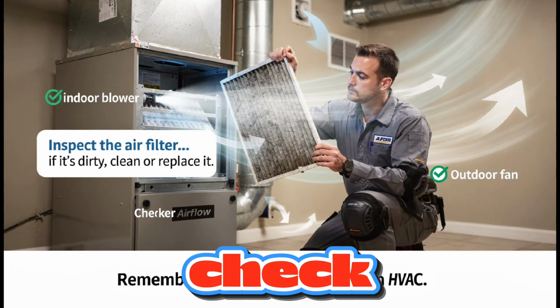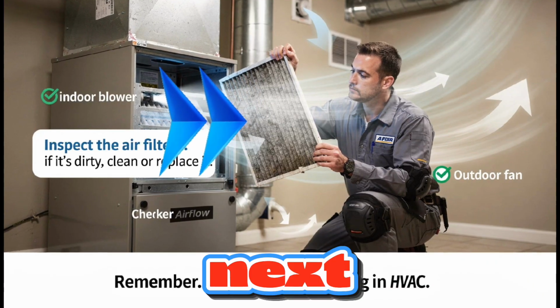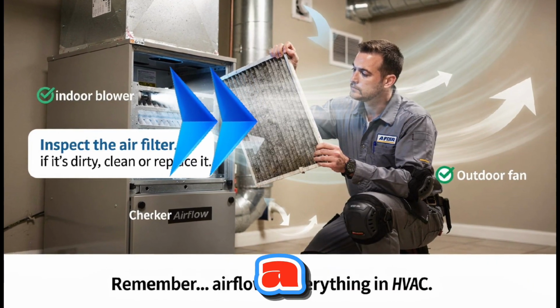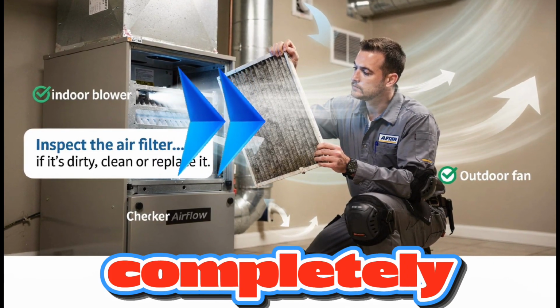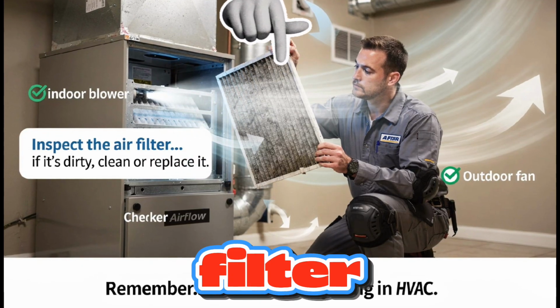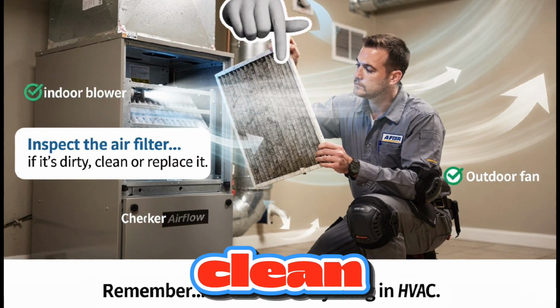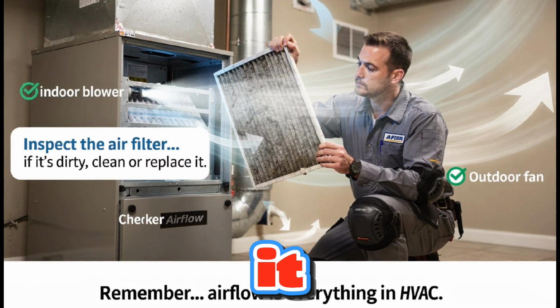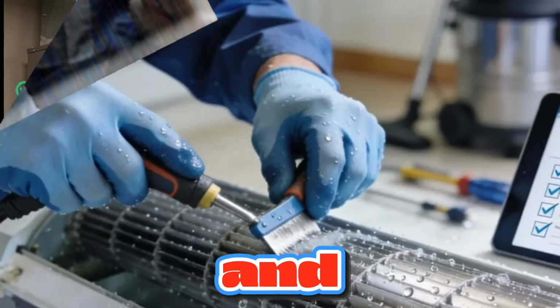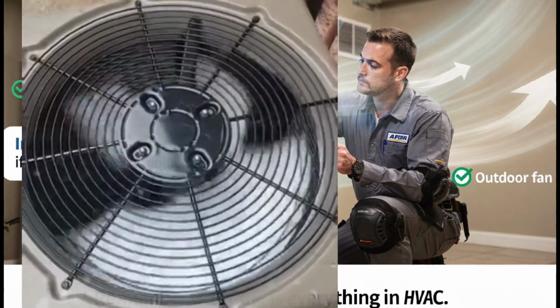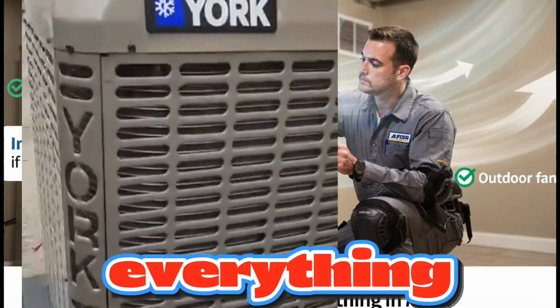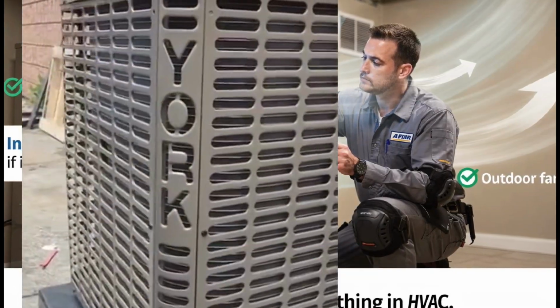Step 2: Check airflow. Next, check airflow. A blocked airflow can stop cooling completely. Inspect the air filter. If it's dirty, clean or replace it. Also check the indoor blower and outdoor fan operation. Remember, airflow is everything in HVAC.